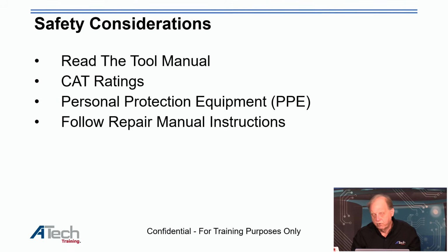On safety considerations, when you're doing this, you want to read the tool's manual, make sure you're using the tool appropriately and safely in the process. The next thing is you want to look at CAT ratings. Some conventional voltmeters will have a CAT rating of 1,000, but those leads are used with that meter. When you go up to high voltage testing, you want to make sure the leads stay with that meter and are assigned to that meter or process. A Megohm meter is going to have a different set of leads than your digital voltmeter does, so you have to make sure you're looking at it.